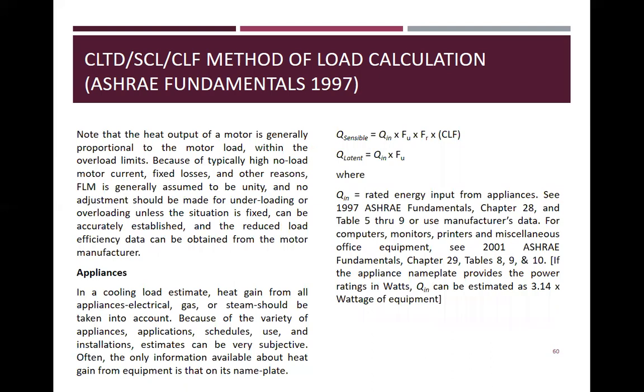Note that the heat output of a motor is generally proportional to the motor load within the overload limits. Because of typically high no-load motor current, fixed losses, and other reasons, FLM is generally assumed to be unity, and no adjustment should be made for underloading or overloading unless the situation is fixed, can be accurately established, and the reduced load efficiency data can be obtained from the motor manufacturer.